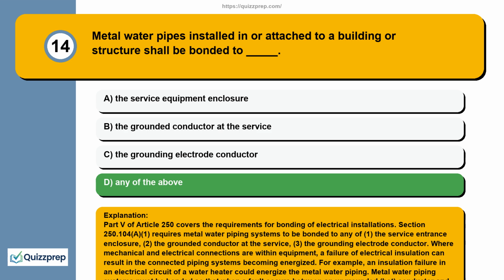Metal water piping systems must be bonded so that when a fault occurs between an ungrounded, hot, conductor and the piping, the potential difference between the two is minimized, thereby reducing the risk of electrical shock. Also, note where installed in or attached to a building or structure, all metal piping systems, including gas piping, that is likely to become energized shall be bonded to a grounded source. 250.104, B.